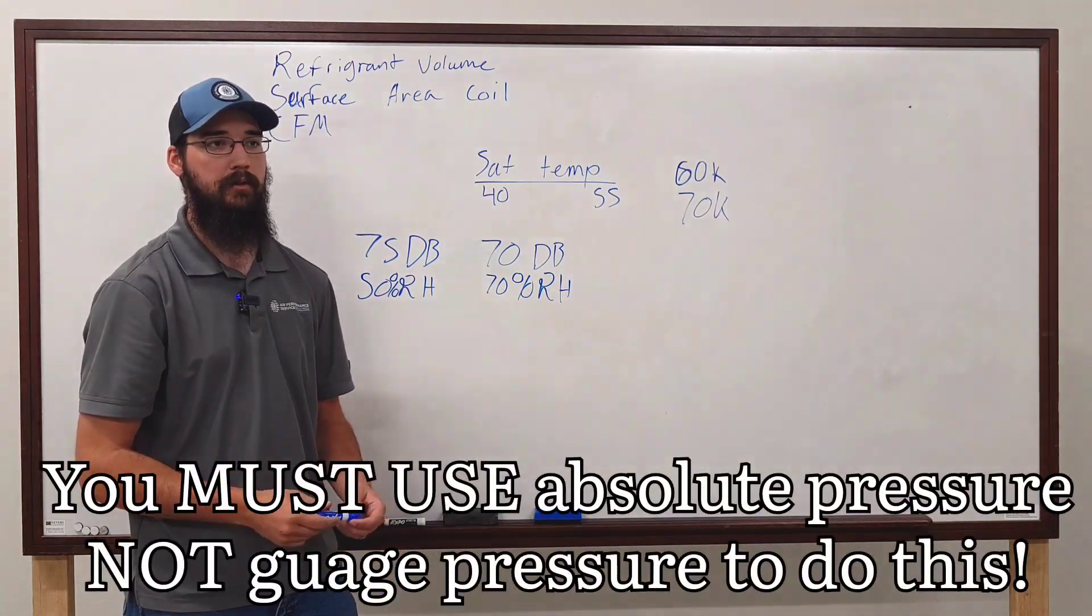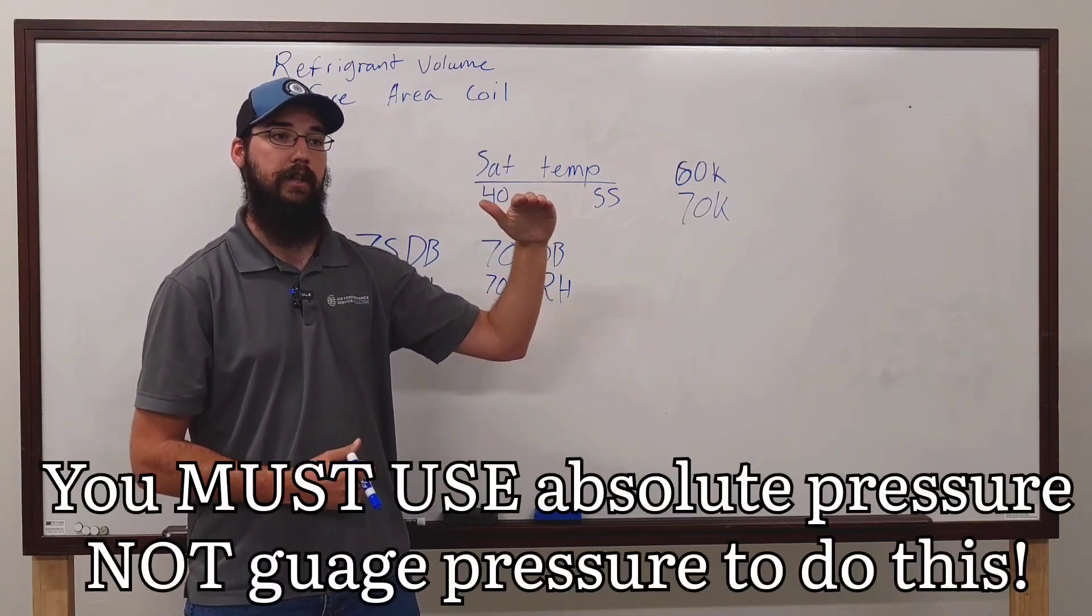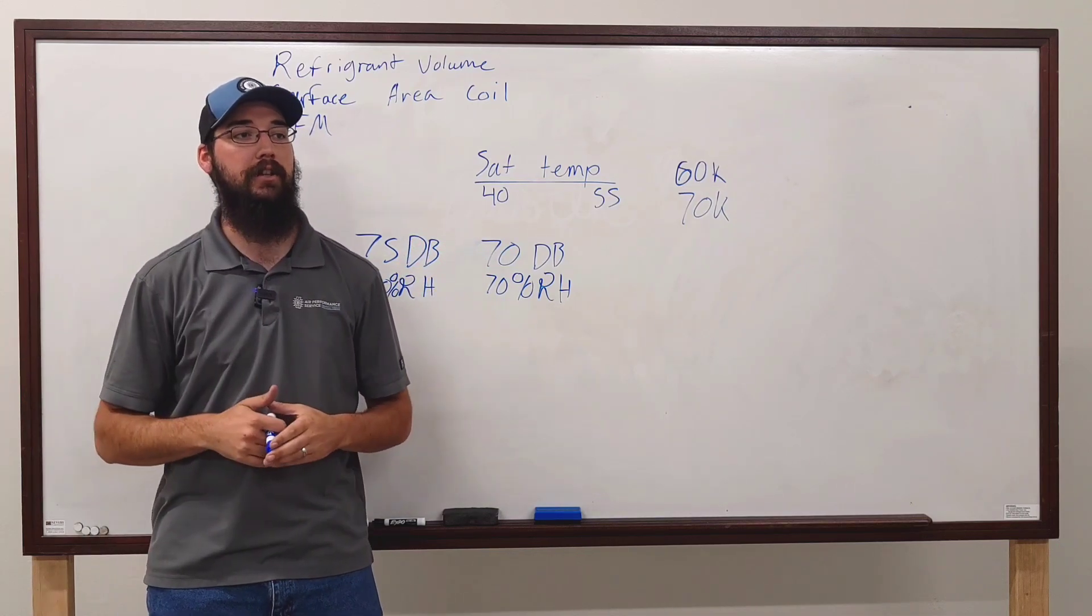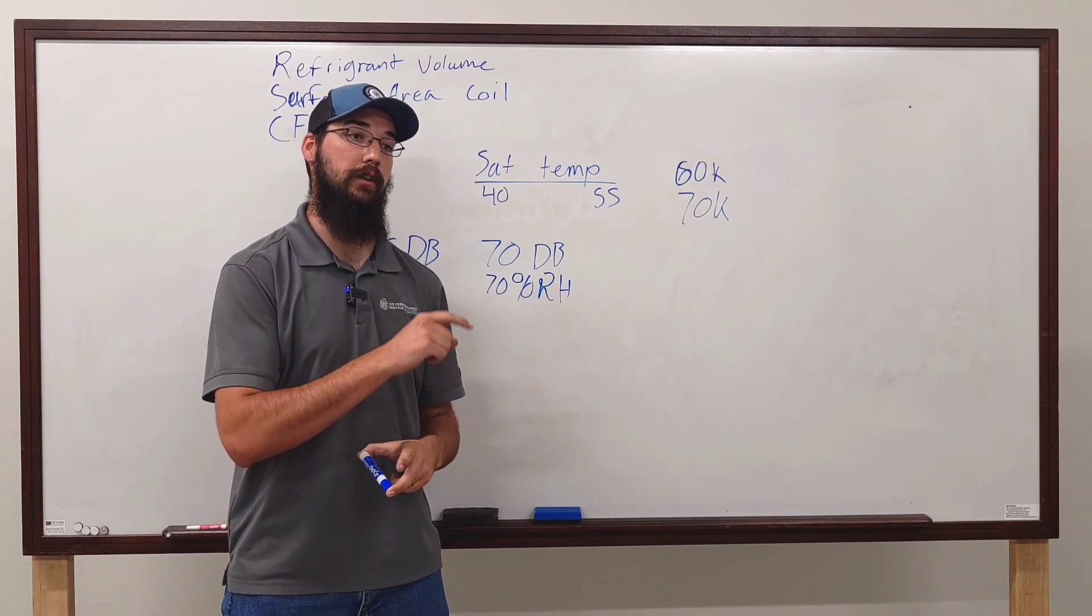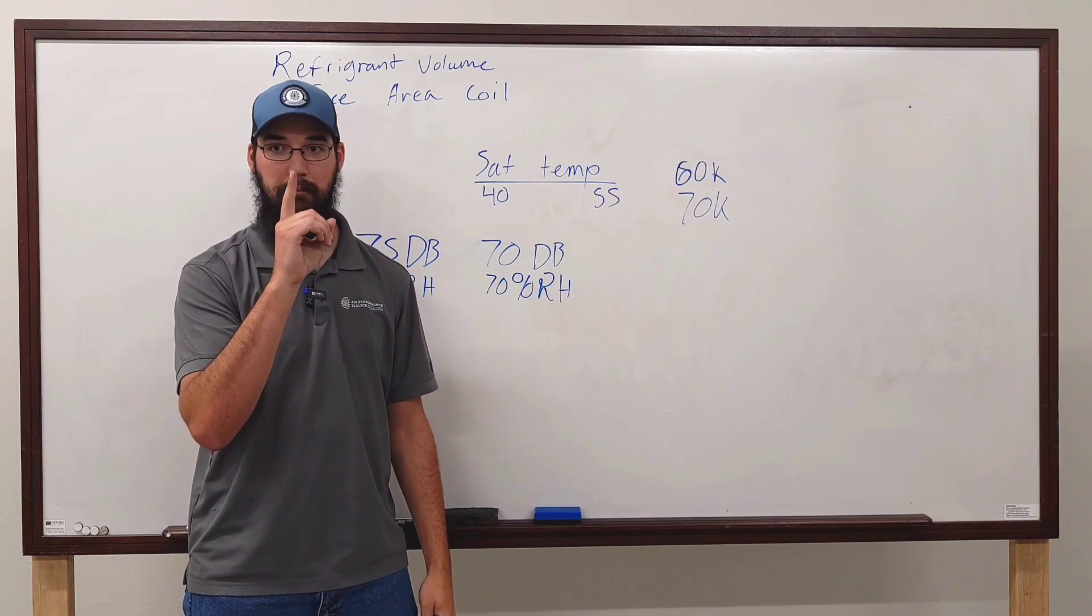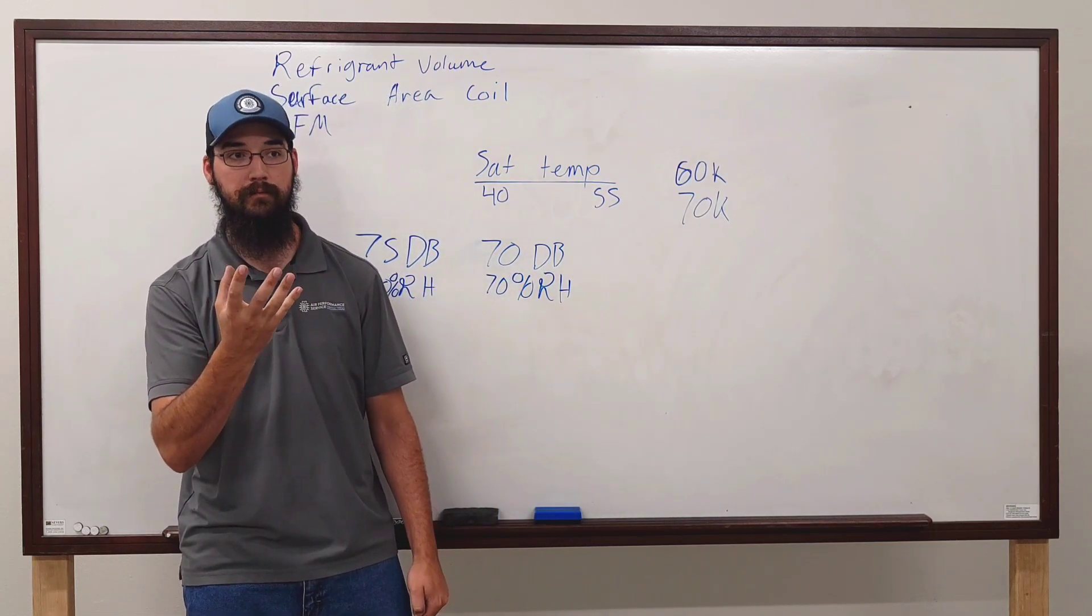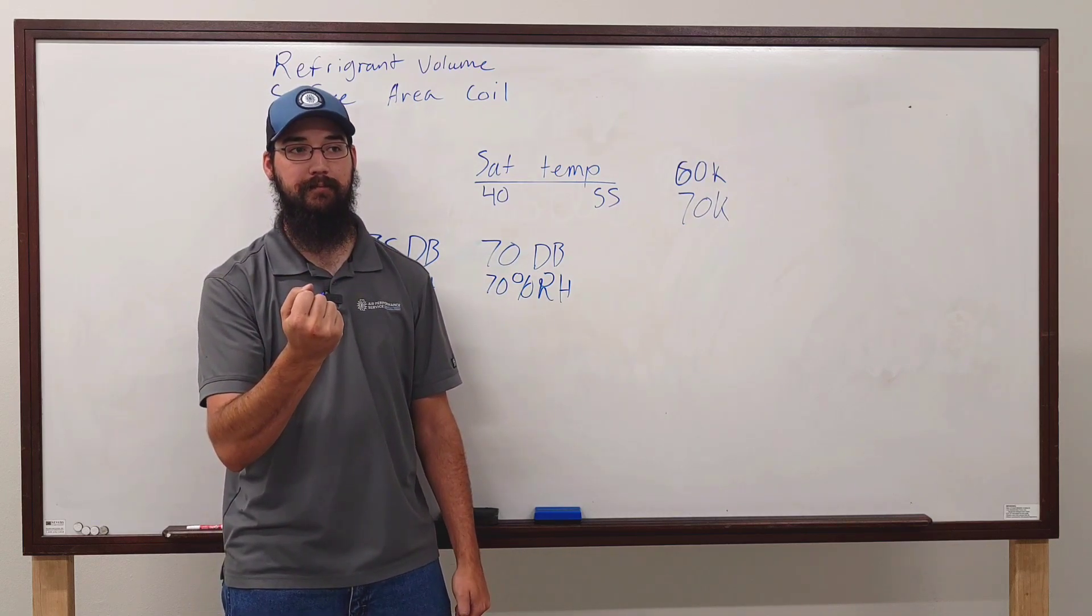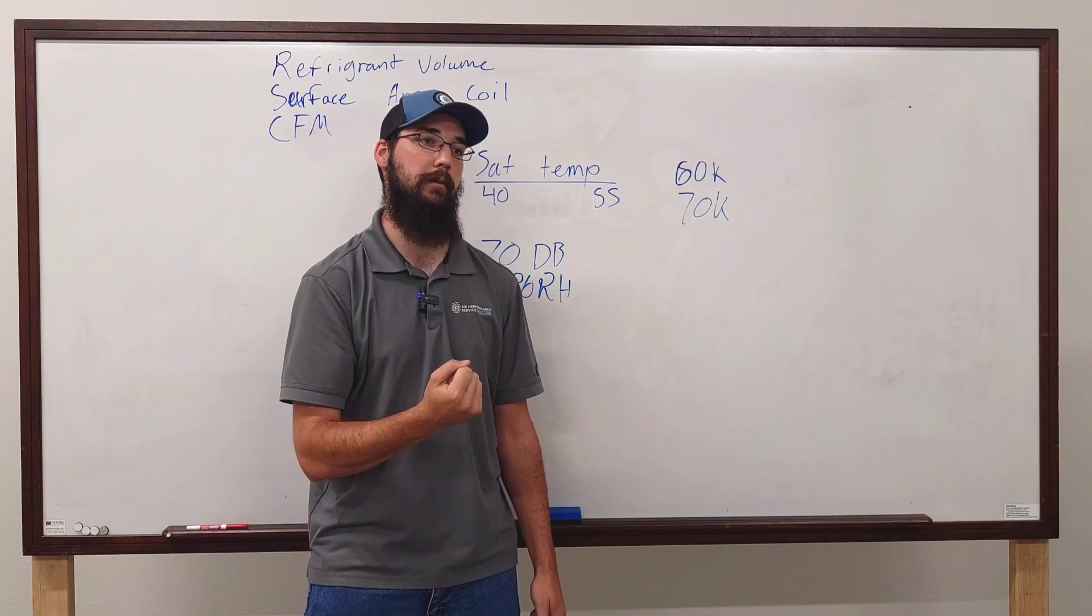You don't know how to calculate compression ratio? You essentially just divide your discharge pressure by your suction pressure. That gives you your compression ratio. Once you start exceeding on the high end of that ratio, you've got a very inefficient system. But at the same time, you can't go too low on that number, because what does it mean when your compression ratio is one? You're not pumping squat. What do we call a compression ratio of one or near one? Say it's 1.2. It's inefficient. Valves are bad, plates shattered. We go down the list. That compressor has failed somehow.